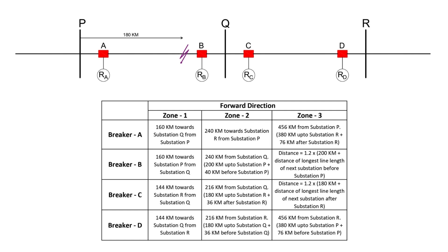Now, let's assume the fault occurs 180 kilometers from substation P. From substation Q, the fault is only 20 kilometers away, so relay B will detect it as a zone 1 fault and trip instantaneously. But from substation P, the fault is outside zone 1 reach, so relay A will detect it as a zone 2 fault. Since zone 2 has a delay, breaker A won't trip immediately.